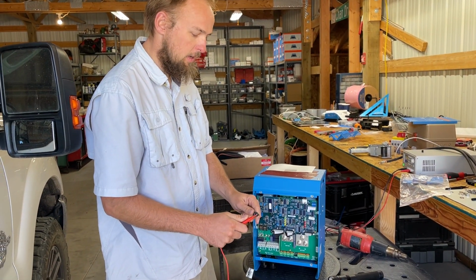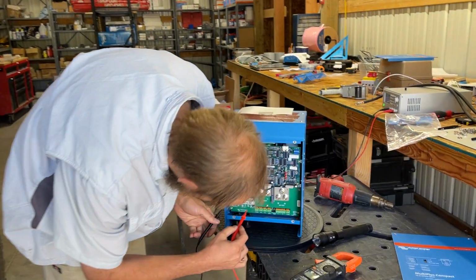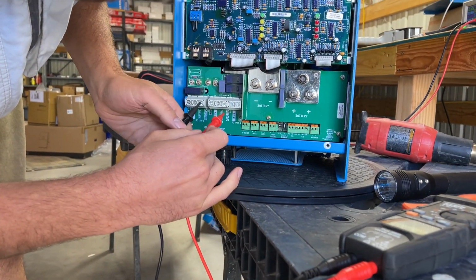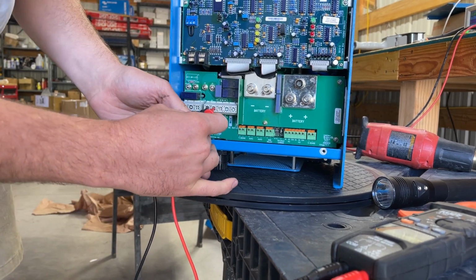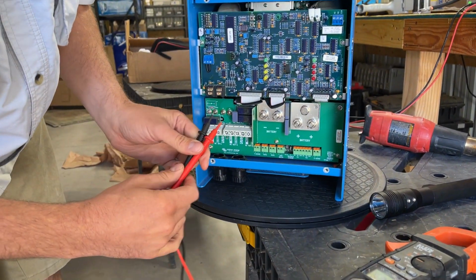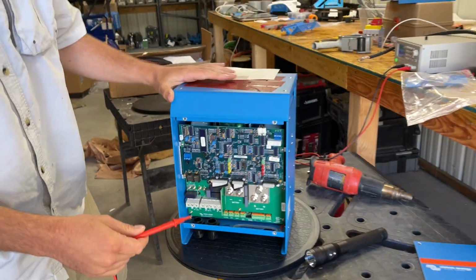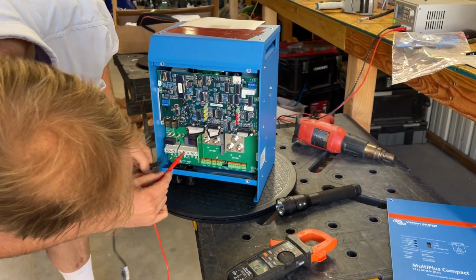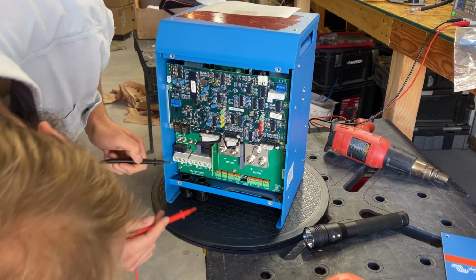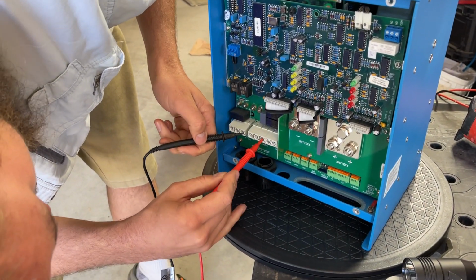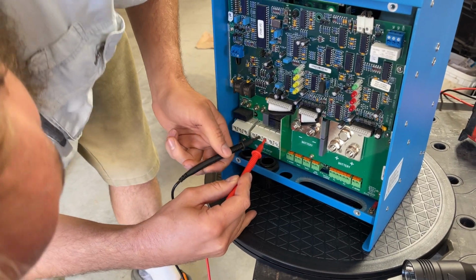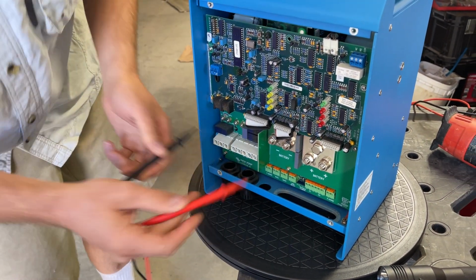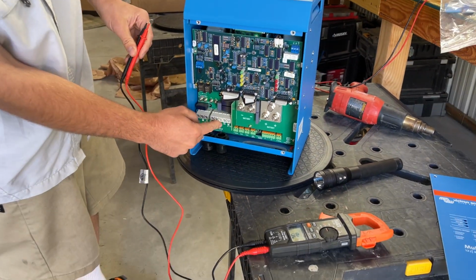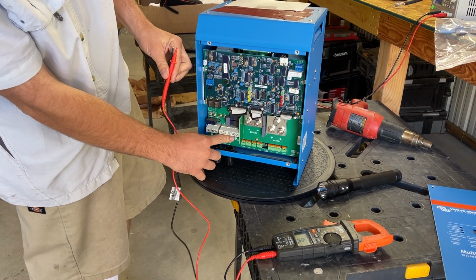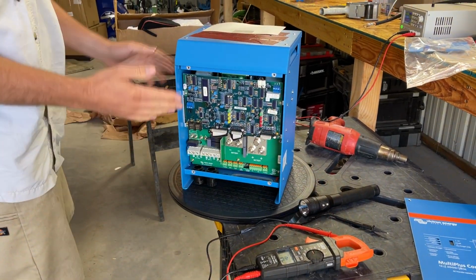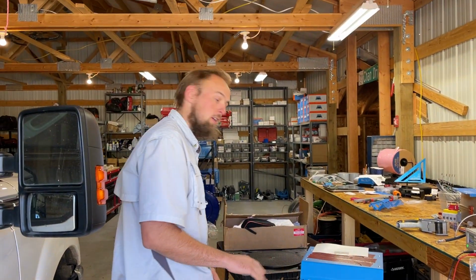So I've got my continuity tester here, and we can see that indeed at AC out 1, there is continuity between line and neutral. So it is as described. And there is no continuity between neutral and ground currently. Where's ground? On some equipment, there's no continuity here. Some will say ground and some will say PE for potential earth. So let's go to the whiteboard and see what's going on.